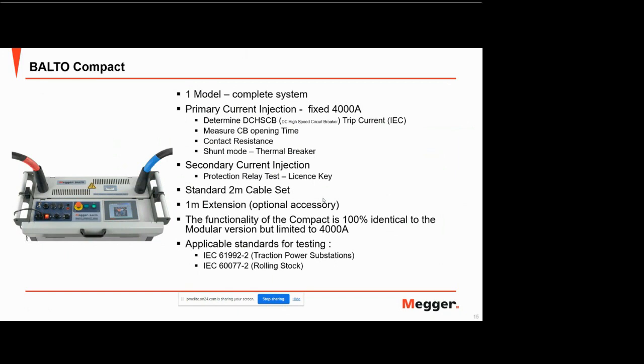Again, like the modular, the compact will also do your secondary current injection, so you can test your relays. And again, it comes with the standard 2-meter cable set and the 1-meter extension, which is an optional accessory. But just to be clear, the functionality of the compact is 100% identical to the modular. The main difference here is that it's fixed at 4,000 amps. And again, that's really for rolling stock applications. But it's applicable for both standards because of the 200 amps per second current rising slope that both the modular and the compact support.